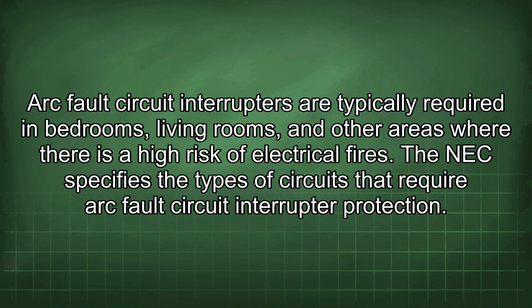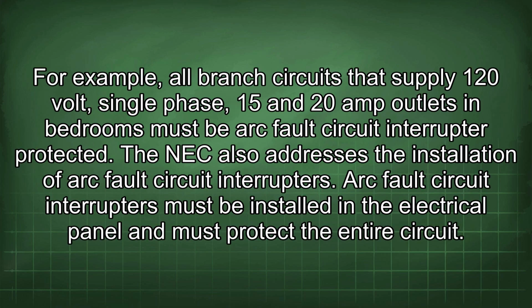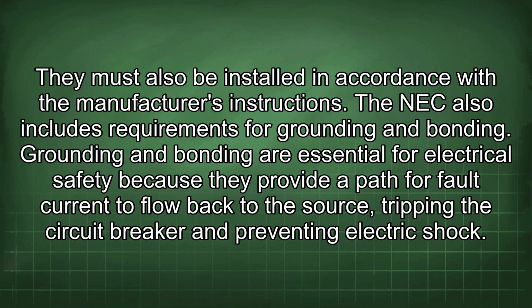The NEC specifies the types of circuits that require arc fault circuit interrupter protection. For example, all branch circuits that supply 120 volt single phase 15 and 20 amp outlets in bedrooms must be arc fault circuit interrupter protected. The NEC also addresses the installation of arc fault circuit interrupters. Arc fault circuit interrupters must be installed in the electrical panel and must protect the entire circuit. They must also be installed in accordance with the manufacturer's instructions.